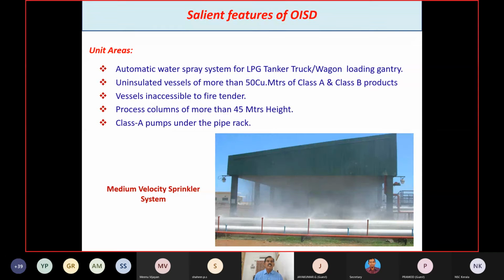Unit area automatic water spray system for LPG tanker, truck and wagon loading gantries, and uninsulated vessels of more than 50 cubic meters of Class A and Class B products, vessels inaccessible to fire tenders, process columns of more than 45 meters height, and Class A pumps under the pipe rack. For all these we should provide a sprinkler system.